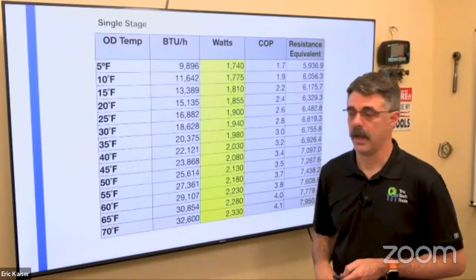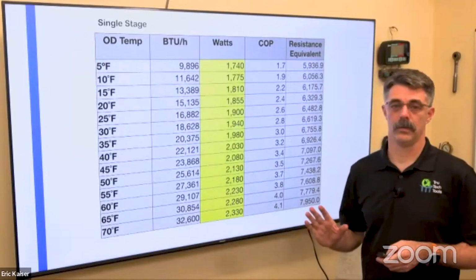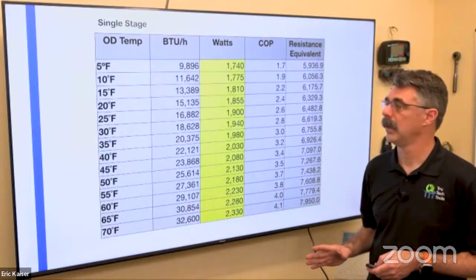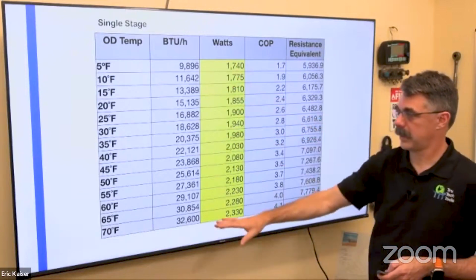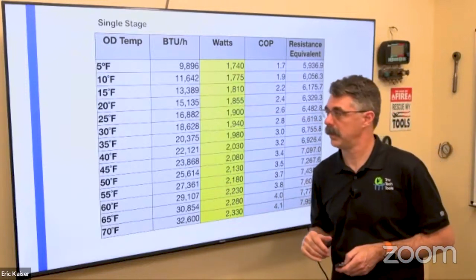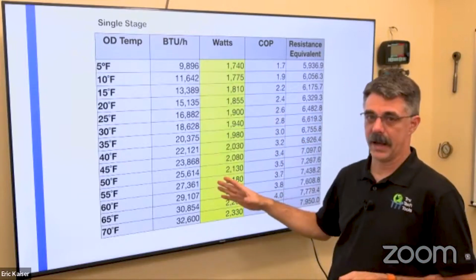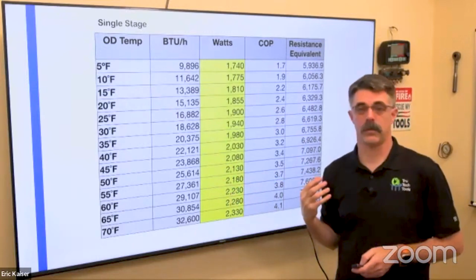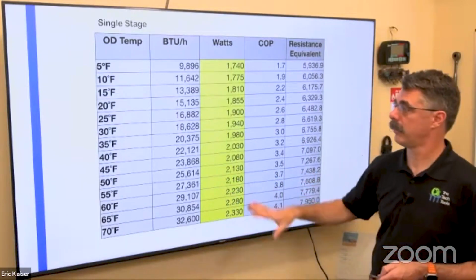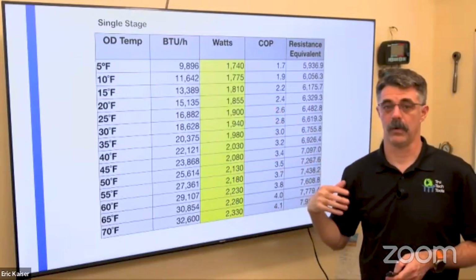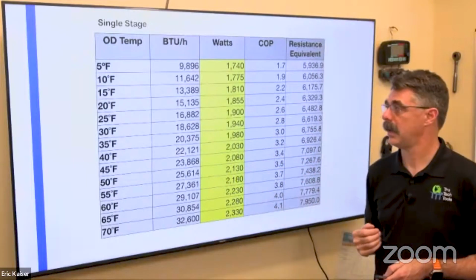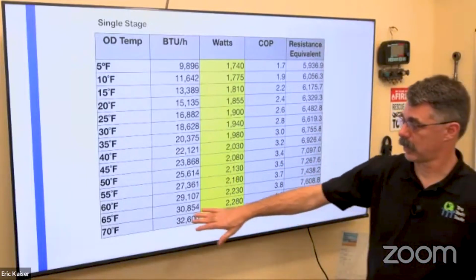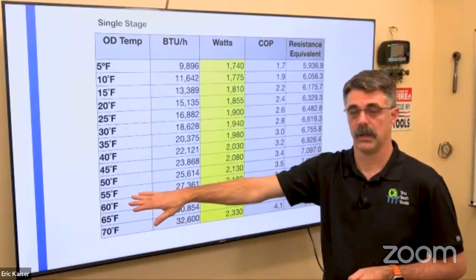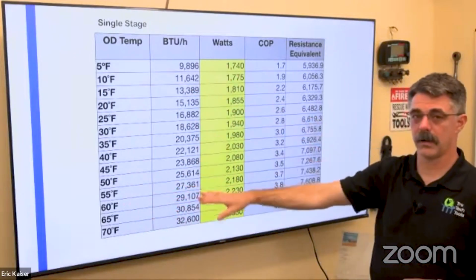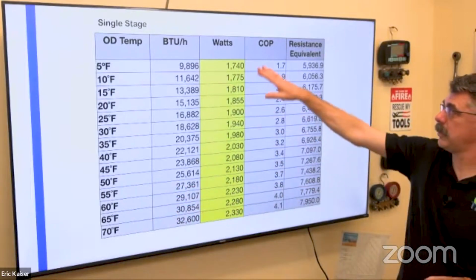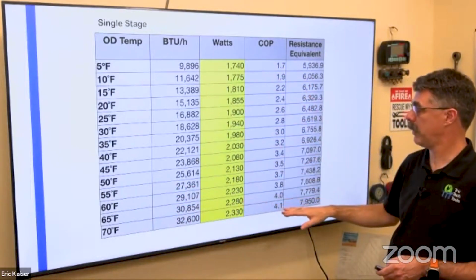All right. Now, this is where we get into knowing a little bit about how this operates. And a lot of times we're going to have, to Keith's earlier question, in a data sheet from the equipment, it's going to have a lot more information in it than this. It's going to say what airflow that's operating at, things like that. But this shows a correlation between outdoor temperature, right, delivered BTUs per hour, how many watts I'm using, what my COP is.